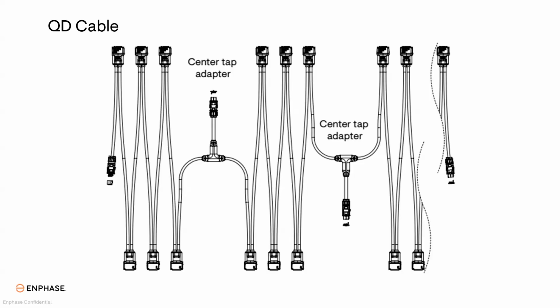And these are pre-installed. You don't have to do anything. All you've got to do is pull out the sealing cap that's on that pre-installed connection and install a male field wire. We'll plug it in, and you can run your home run power over to your junction box or combiner panel.